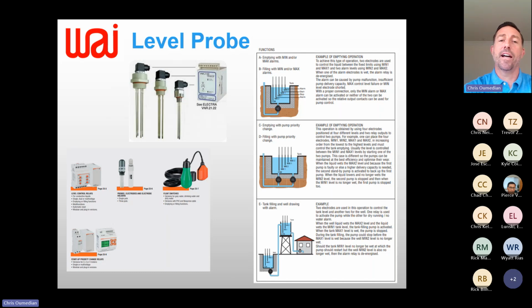I believe this is our last slide. So the capacitive is a non-contact discrete, very popular, been around forever, traditional level probe. There's a couple of ways to do it. You'll see up here on the left, conductive probes. So these are probes of varying lengths, similar concept to the capacitive, where you would have one with a short probe for your high level, and then another one of these devices with a really long probe. These can go way longer than 2 meters that stick down in the tank. And as the media touches those 2 probes, you close the circuit and you'll conduct across the probes, and it says the liquid level's here or the liquid level's here.